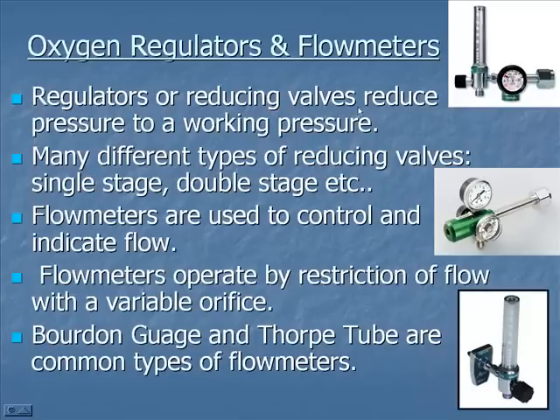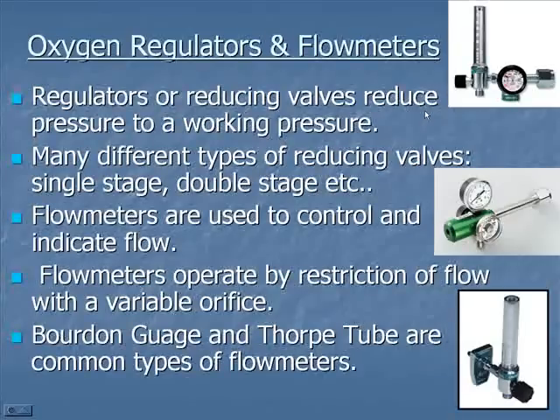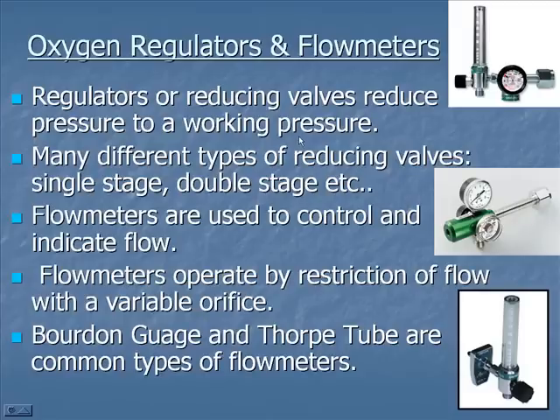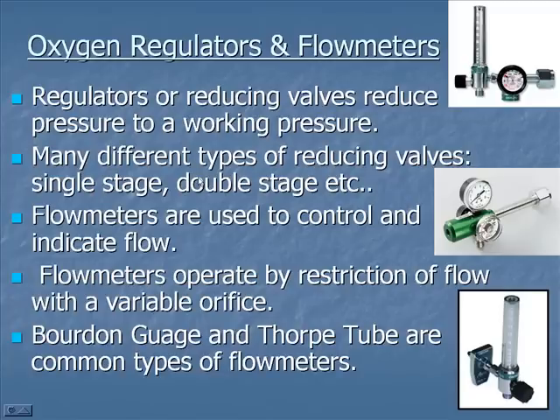That brings us to the regulator portion or flow meters. Once the liquid oxygen is piped and turned into a gaseous state through the hospital piping system, we need a way to deliver that gas to the patient. It comes through the piping at around 50 psi, so we've got to reduce it down. We have a variety of flow meters or regulators designed to reduce it from 50 psi down to a flow we can deliver to the patient.